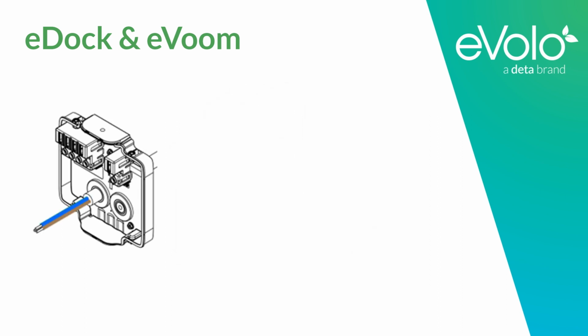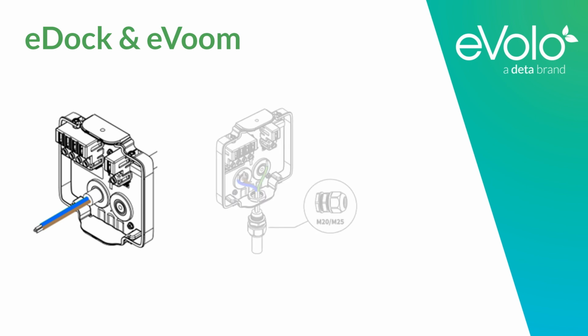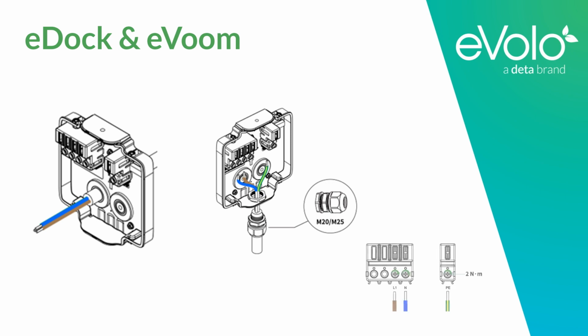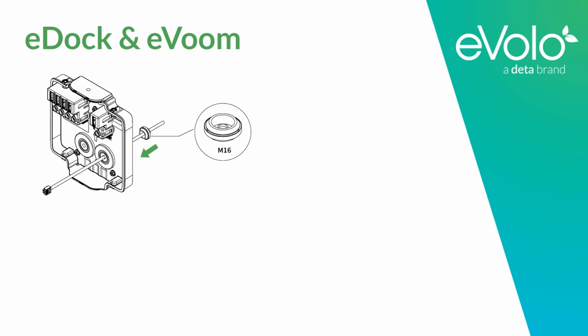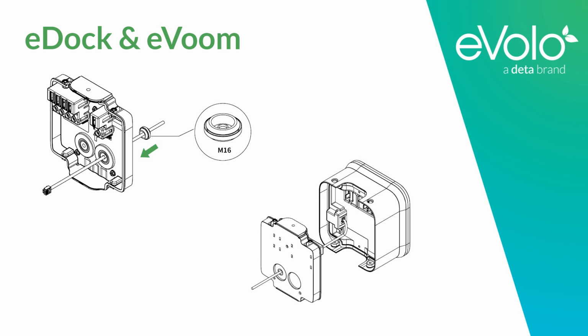Wiring couldn't be easier. Ideally, cables will be routed through the rear of the mounting base to provide neater installation. Once you have brought your cables through the entry point, use a grommet provided or a cable gland to connect the power cables, terminating the conductors and tightening the screws to 2 Newton-meters of force. All Evolo terminals are suitable for 10mm squared cables. If fitting a data cable, drill out the cable entry point and use the grommet supplied. The data cable will need an RJ45 plug fitted, plugging into the port on the rear of the charge point.